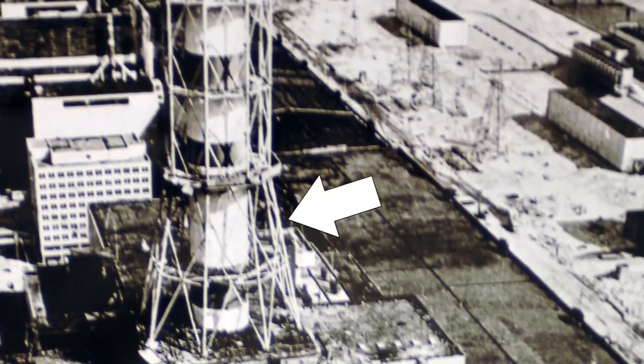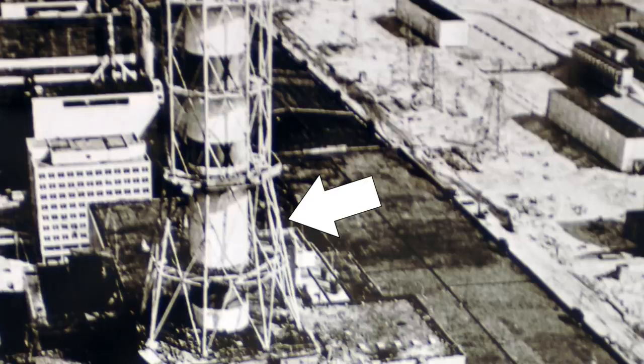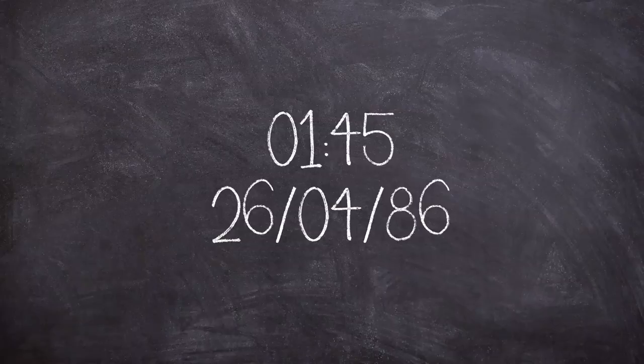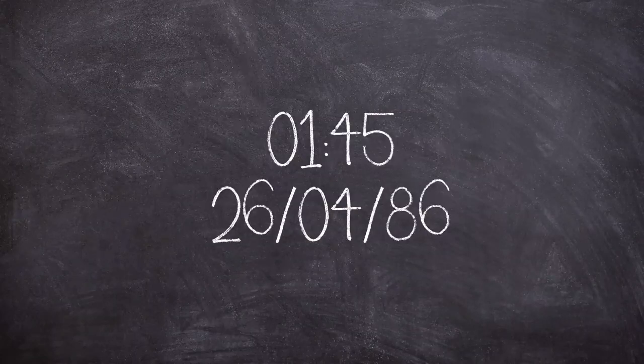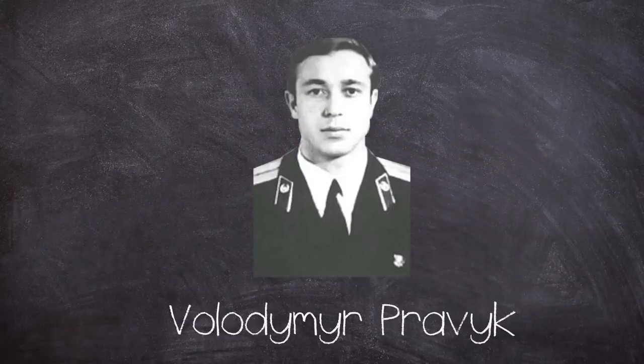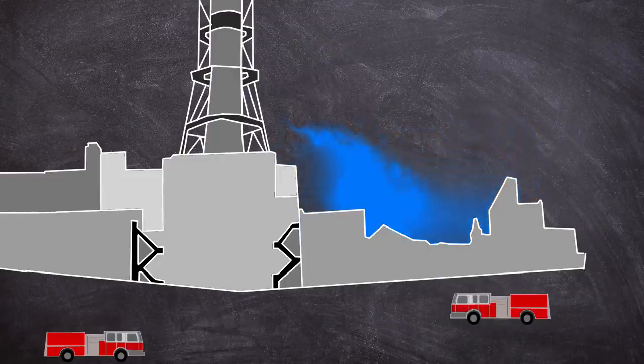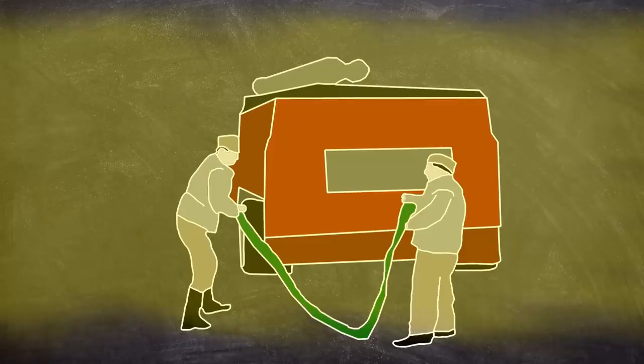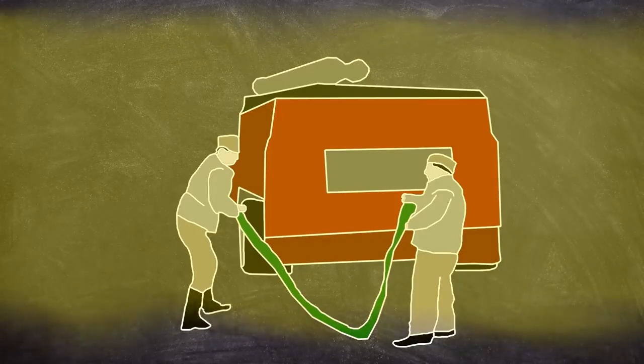Some of the debris ejected started a fire on the roof of reactor 3's building, but insanely the unit wasn't shut down straight away. Instead, the operators were told to take iodine tablets and don respirators. At 1:45 in the morning, the first responders from the Chernobyl fire team arrived under the command of Lieutenant Vladimir Pravik and began trying to extinguish the flames on unit 3's roof. All around them lay pieces of unit 4's graphite core. The firefighters were only aware of the fire, and because of this they didn't have any radiological protective clothing on. As they worked, they breathed in some of the fission material in the form of dust and were exposed to the deadly radiation. Many would come down with acute radiation sickness shortly after.